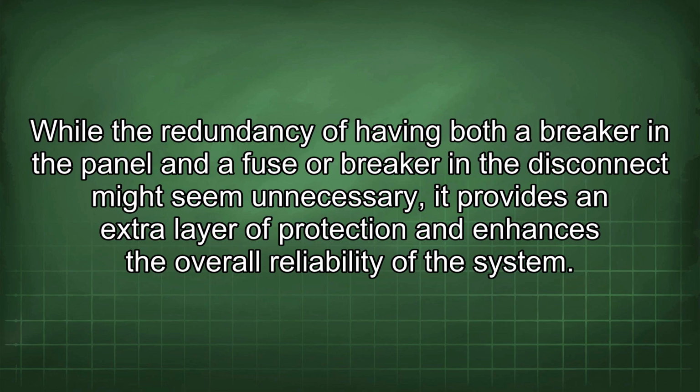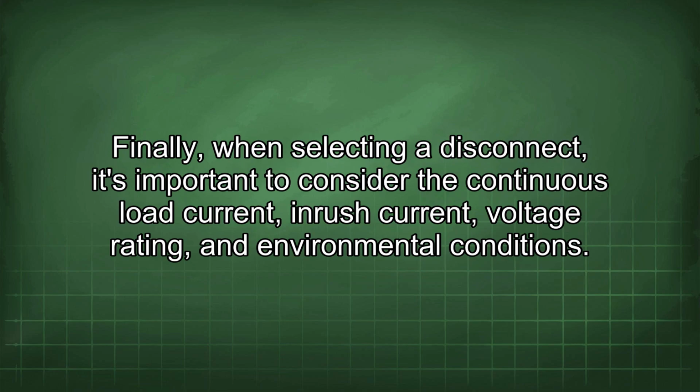While the redundancy of having both a breaker in the panel and a fuse or breaker in the disconnect might seem unnecessary, it provides an extra layer of protection and enhances the overall reliability of the system. Finally, when selecting a disconnect, it's important to consider the continuous load current, inrush current, voltage rating, and environmental conditions.